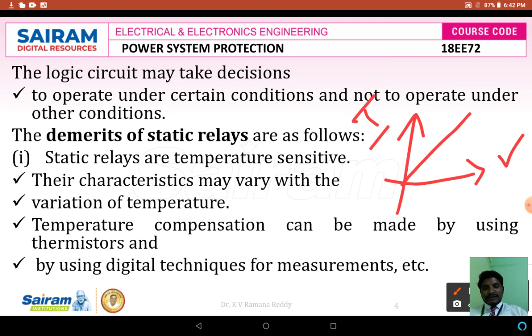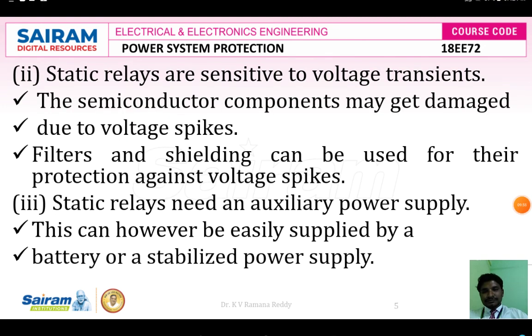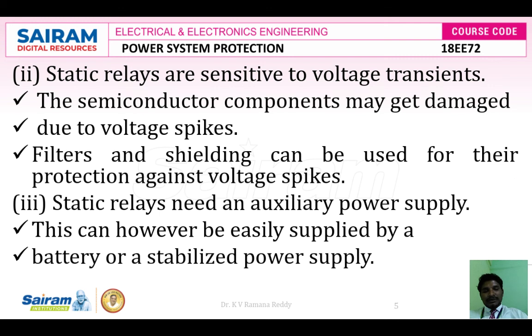The second demerit is that static relays are sensitive to voltage transients and the semiconductor components may get damaged due to voltage spikes. If high voltage comes even for a fraction of seconds, the static relay may get damaged. To protect against voltage transients and voltage spikes or power surges, we must use filters and proper shielding. Also, static relays need an auxiliary power supply, which is an additional source and adds to cost. This can be supplied by a battery or a stabilized power supply but still includes additional cost.